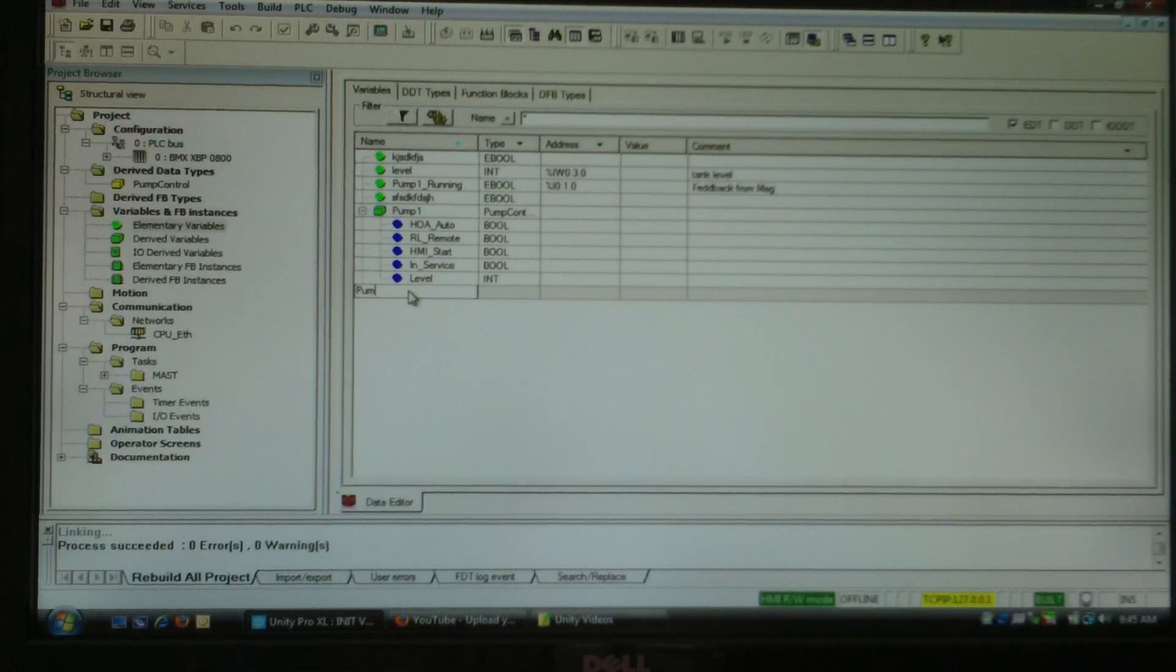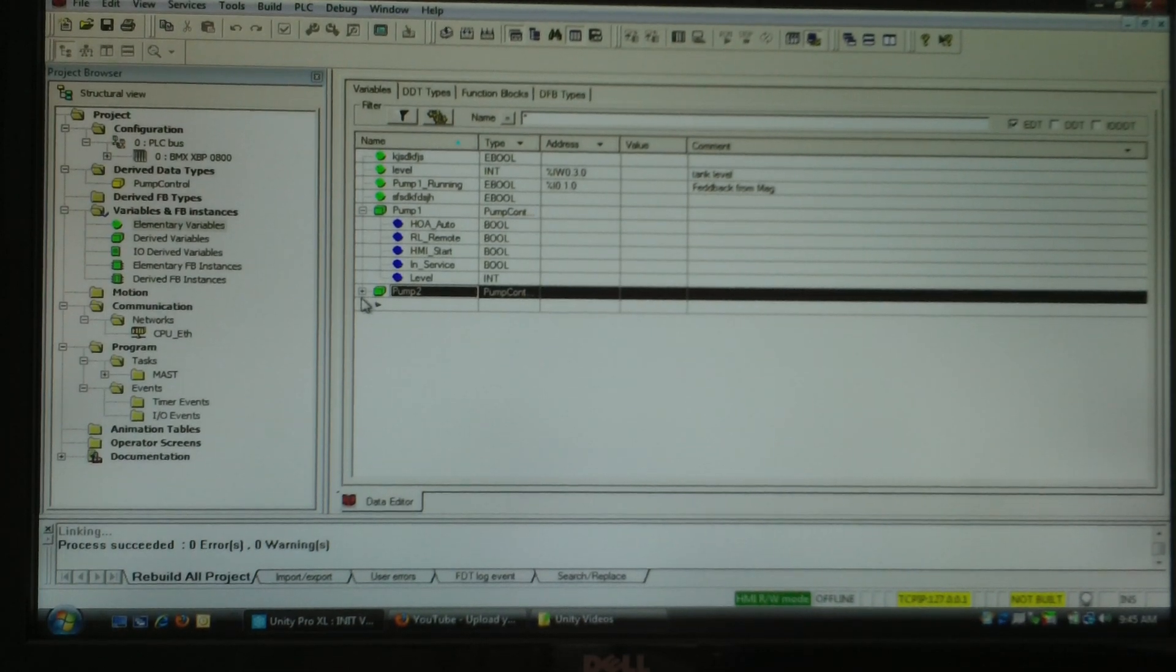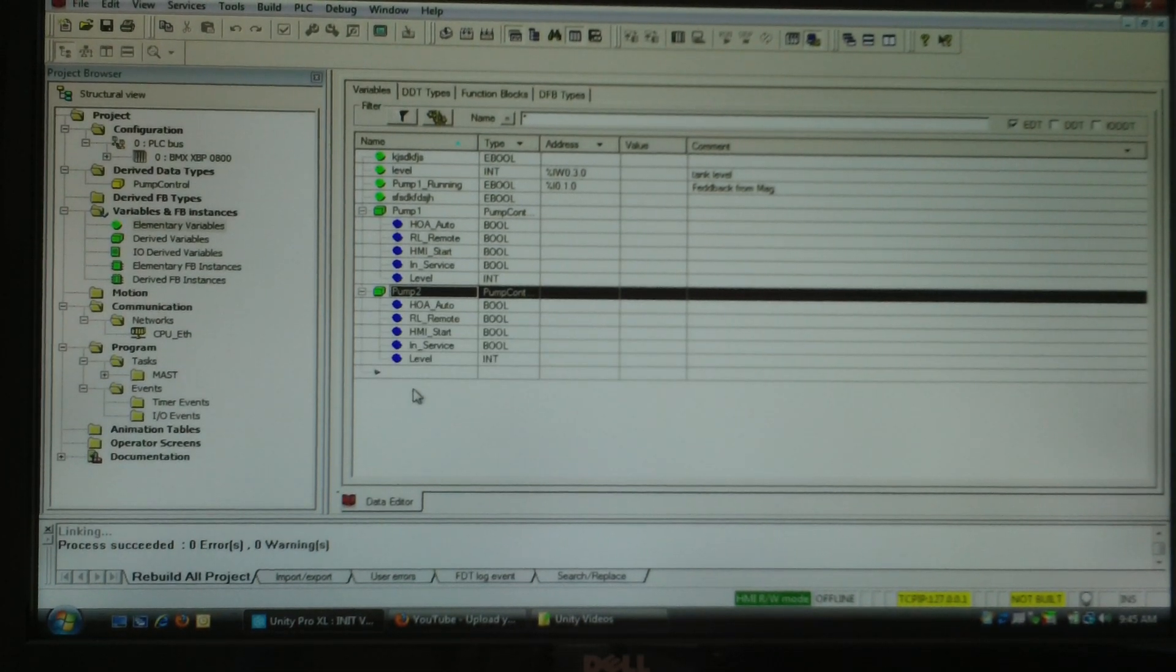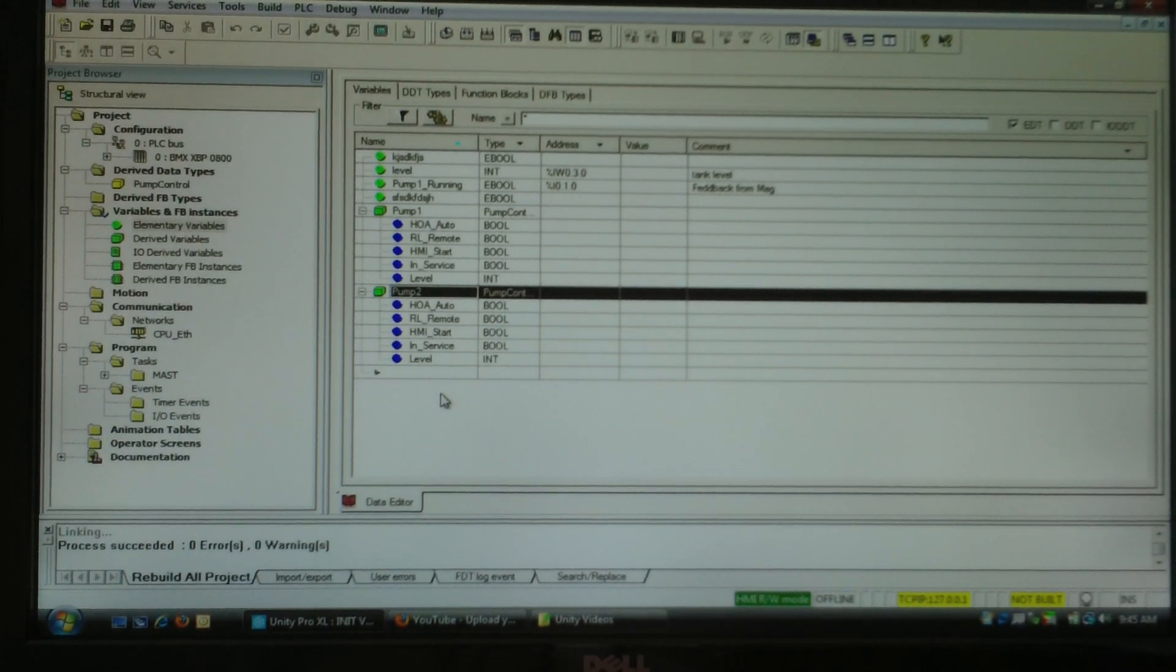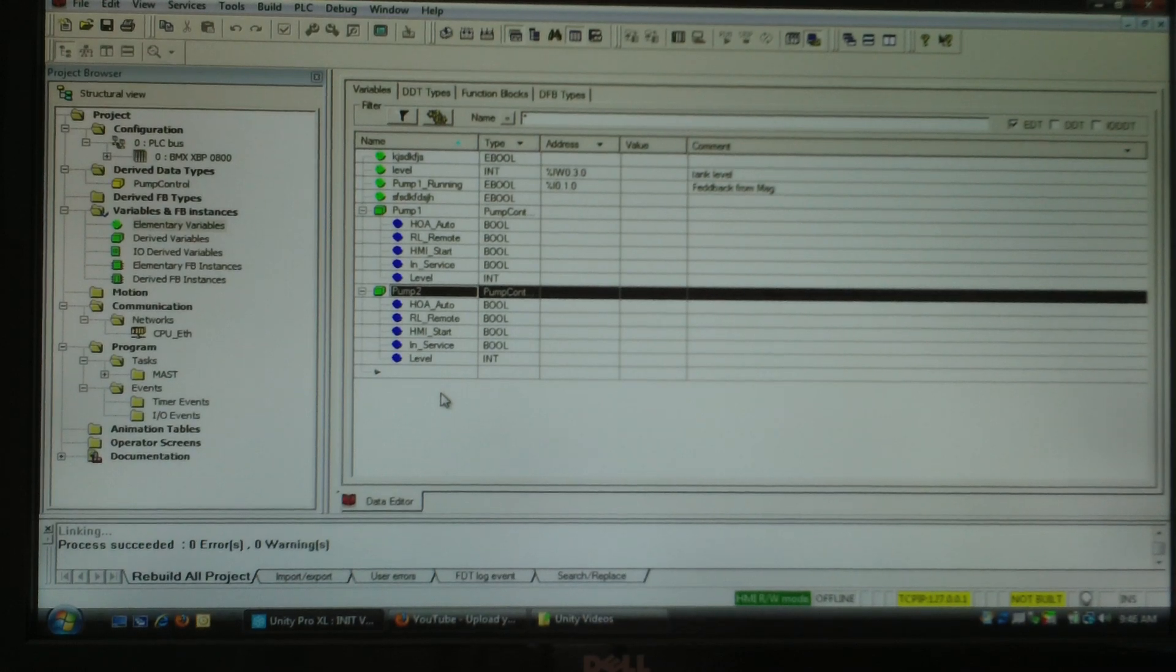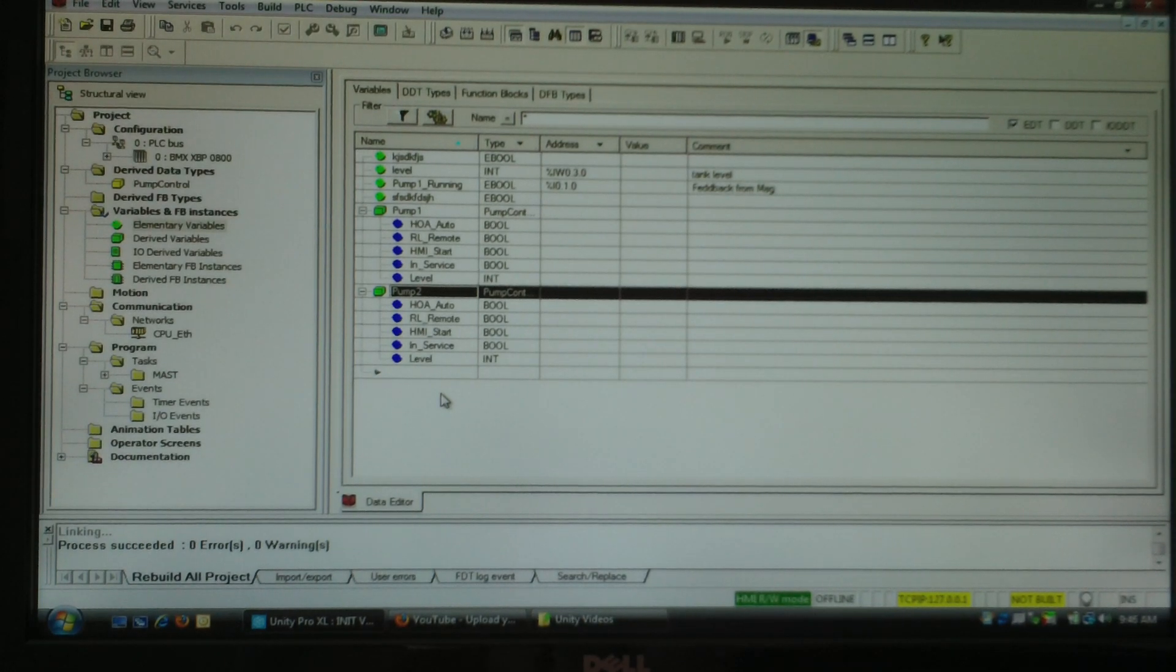Create a pump two. It automatically made it my pump control type, and there's all my tags again. So what I've done is I've automated the process of creating my tags. Every time I add a pump now I can make it that type and bring them in automatically.